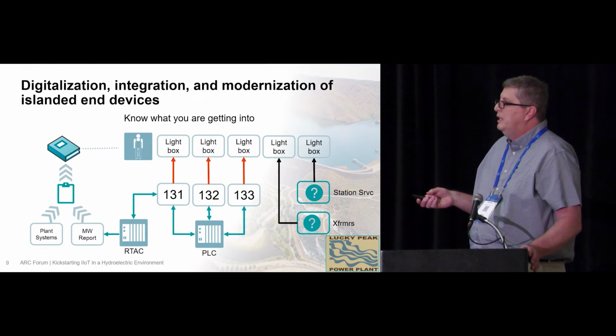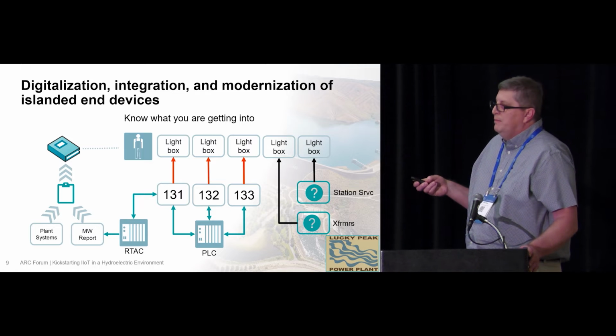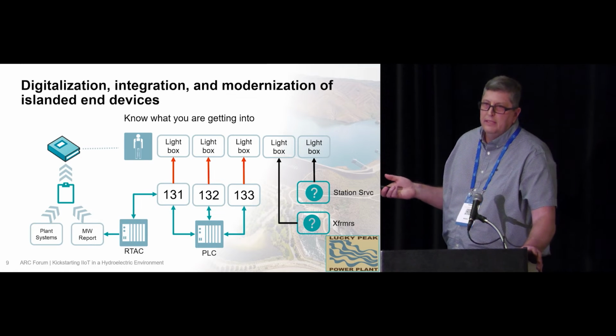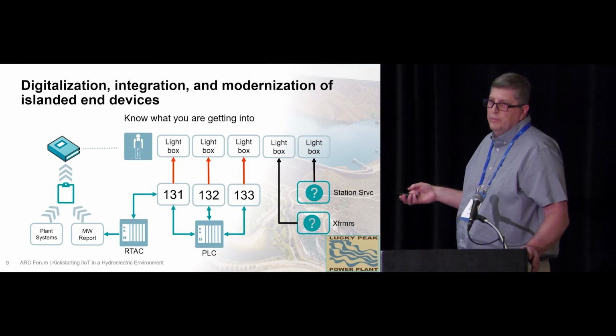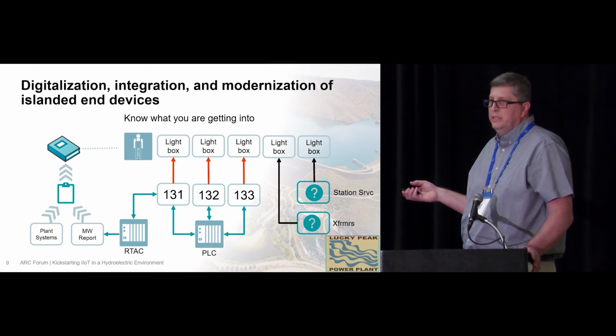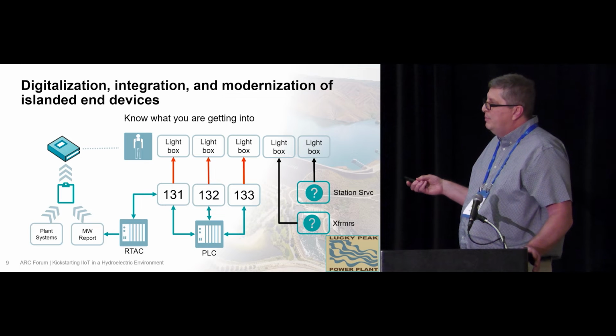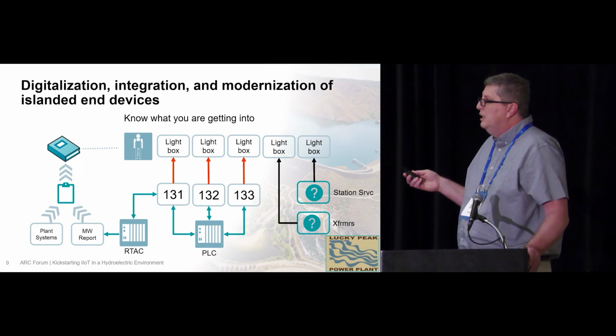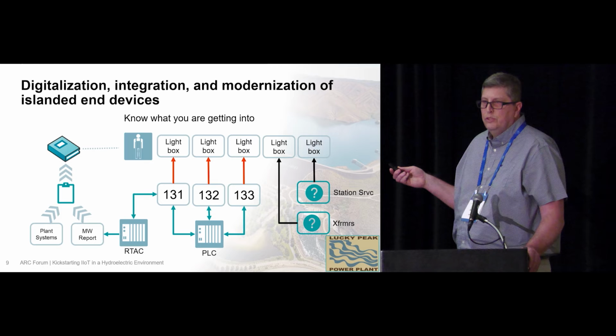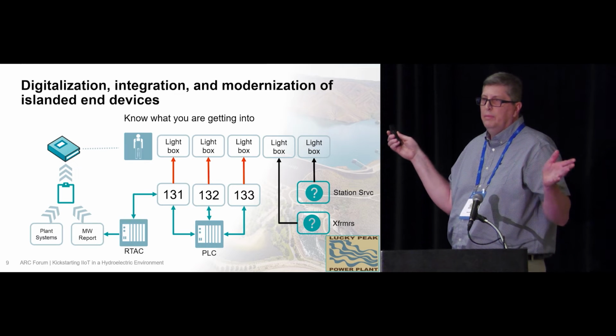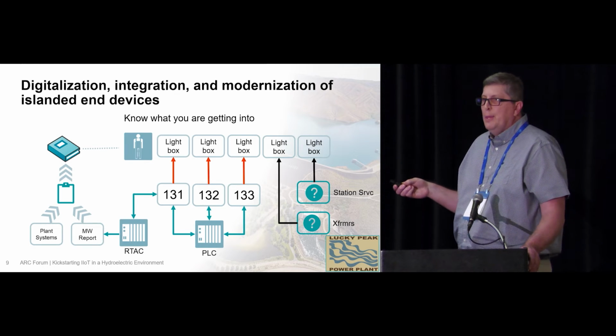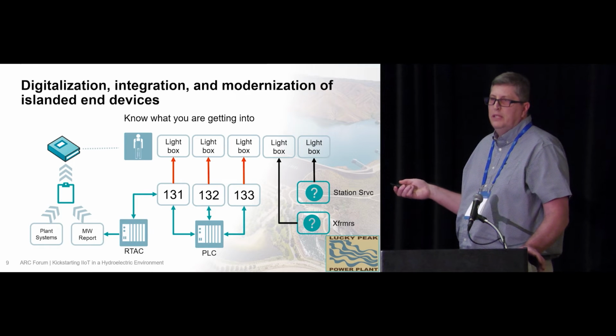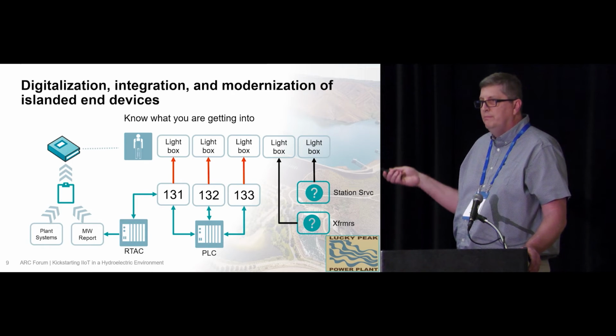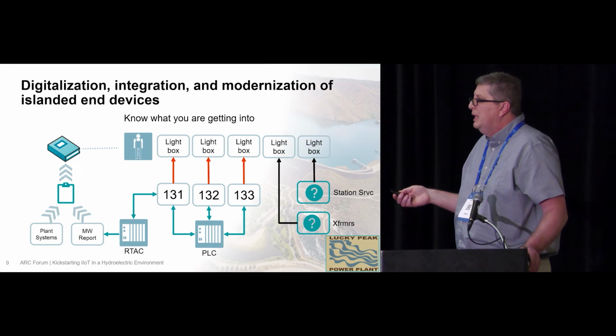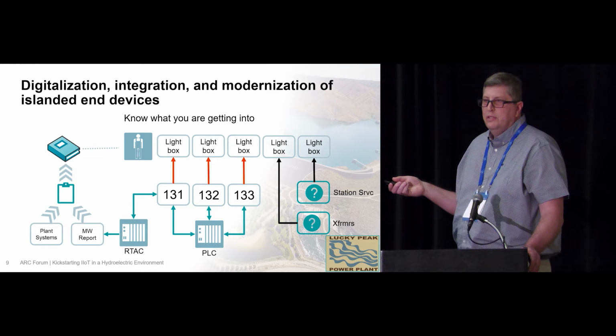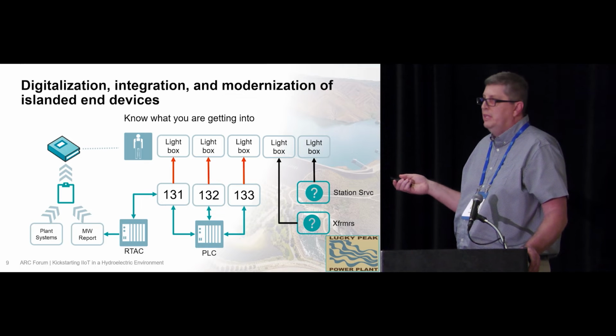So when we look at the integration process, I look at it as we have 5 assets. We have three generators, our transformers, and our station service, which is our 125 volt DC. When we have an issue with one of those, they'll send a signal to a light box that says, hey, here's your problem. Our PLCs basically just do flow control, telling the units a little bit more flow, a little less flow. Along with that, we do have relay protection through our RTAC, which protects all 3 units.